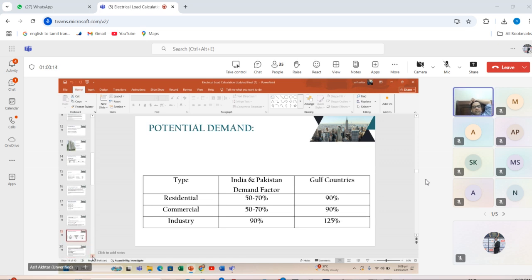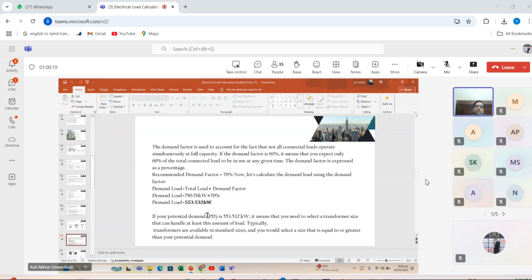Now let's calculate the transformer sizing. The demand factor is used to account for the fact that not all the connected load operates simultaneously at full capacity. This is the most important point. If the demand factor is 60%, it means you expect only 60% of the total connected load to be in use at any given time. So the demand factor is expressed as a percentage. Let's suppose we use a demand factor of 70% in this calculation.